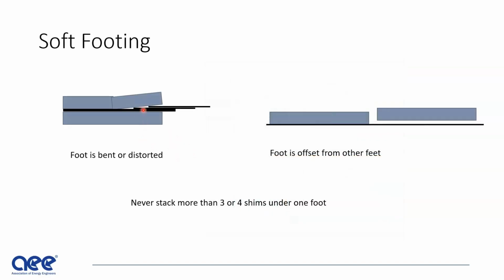Soft footing: here you see shims that are used to align the motor, but when you have a bent foot, you create these air gaps and these shims don't fit properly under the foot. And so you get a foot that is considered soft. And here you see the offset that creates a soft foot. You never want to stack more than 3 or 4 shims under one foot because each shim entraps air between them. When you get enough stacked, it becomes a sponge, and that also creates a soft foot.